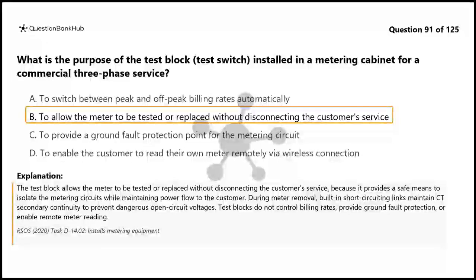The test block allows the meter to be tested or replaced without disconnecting the customer's service, because it provides a safe means to isolate the metering circuits while maintaining power flow to the customer. During meter removal, built-in short-circuiting links maintain CT secondary continuity to prevent dangerous open-circuit voltages. Test blocks do not control billing rates, provide ground fault protection, or enable remote meter reading.